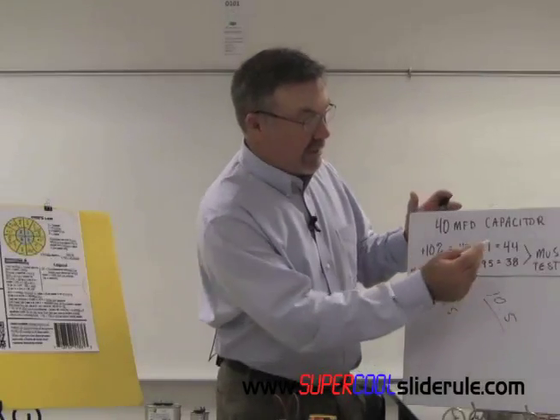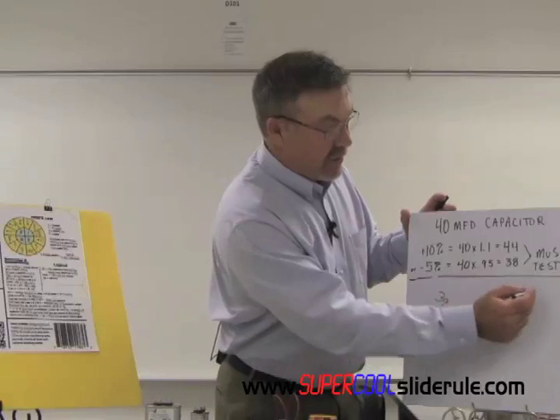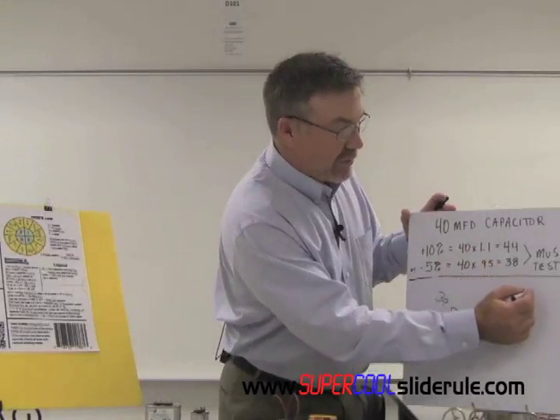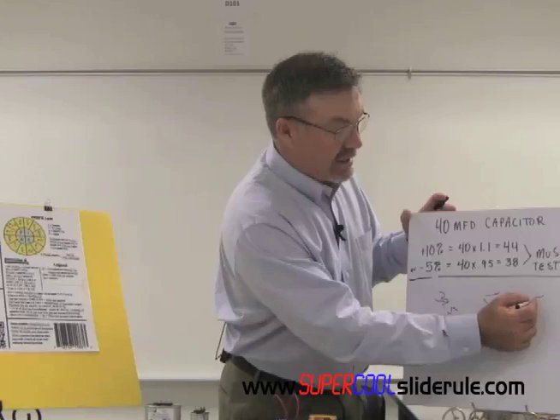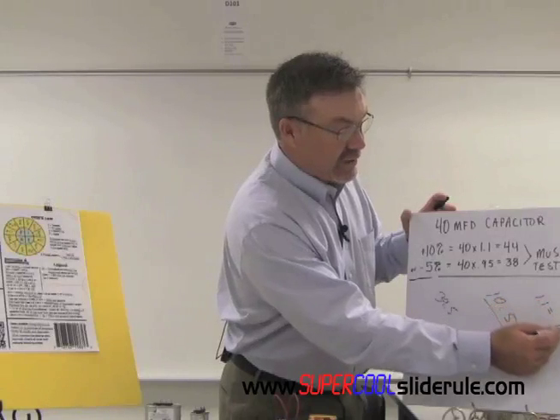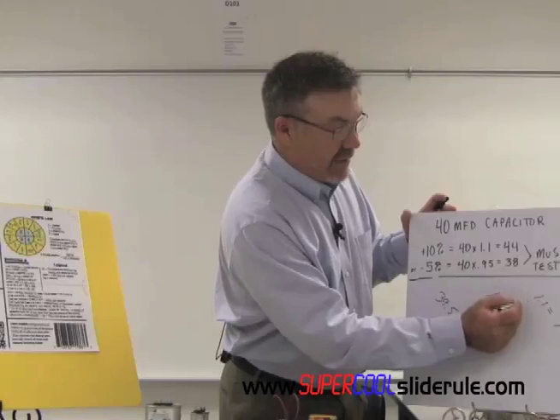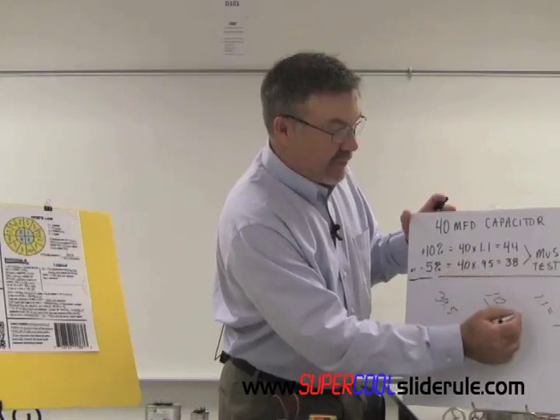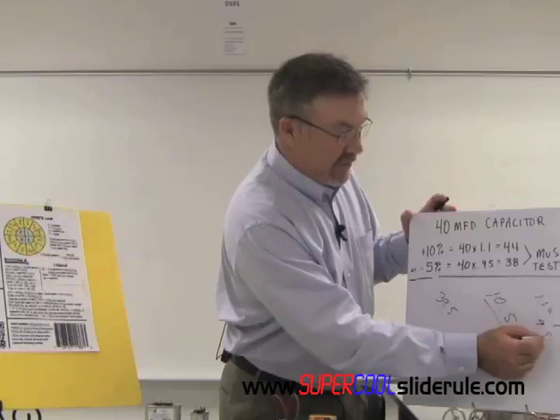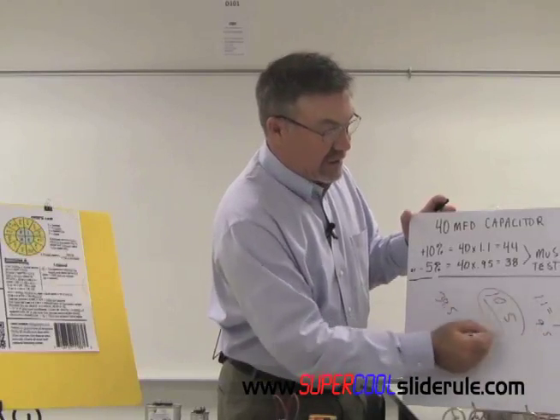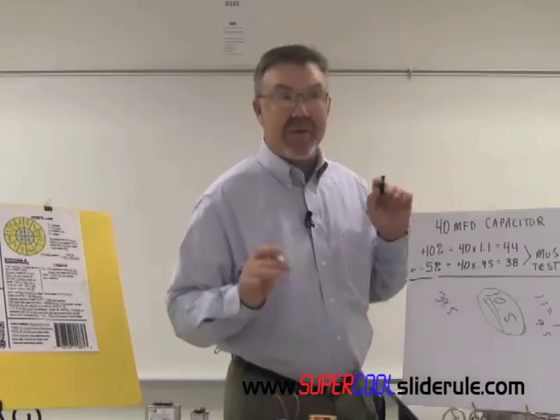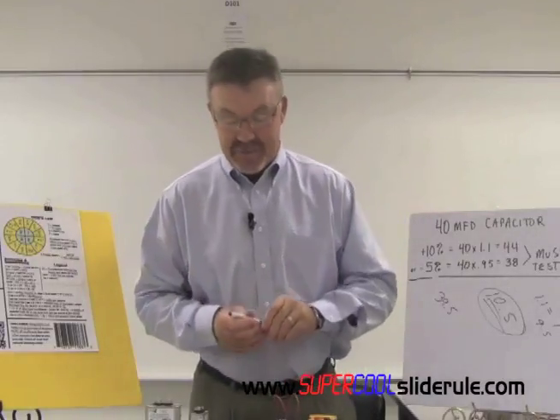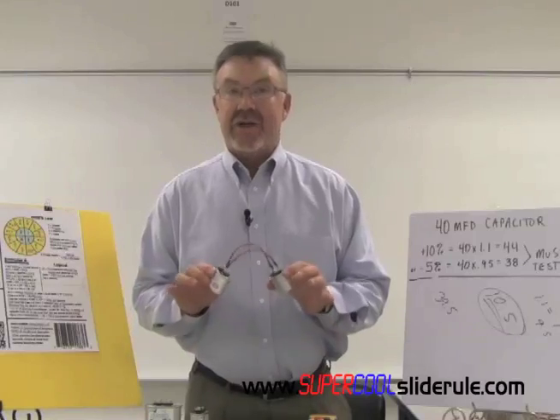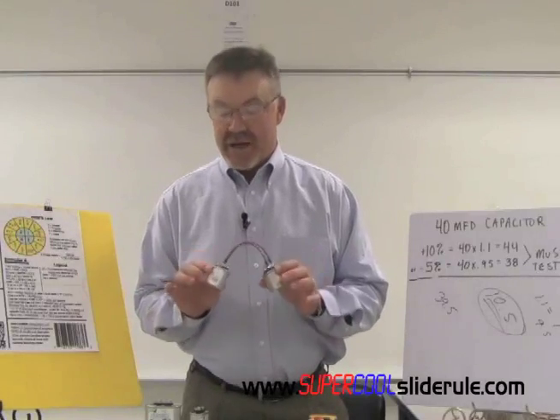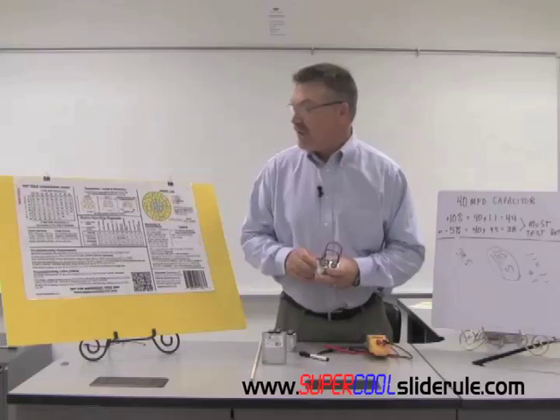Once again, we need to be plus 10% or minus 5%. So on the high side, we'd multiply 10 by 1.1, which would give us 11. Multiplying 10 by 0.95 will give us 9.5. Our capacitor tested out at 10.5. We're within parameters. We are completely fine there. So this was manufacturing a 10 microfarad capacitor with 2 5s that were on the truck.